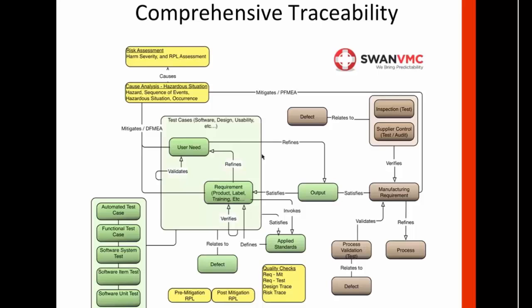So what we want in a requirement is not only to say what the design should do, but what good means. We want to have that acceptance criteria as part of the requirement, whereas the user need could be more general. You know, we want the surgeon to think the handpiece feels good. Well, that's a matter of validation. We'll give it to a surgeon and ask them their opinion, but from an engineering standpoint, we need more resolution. So, you know, what standards are we going to apply? How big should the device be? This kind of thing.